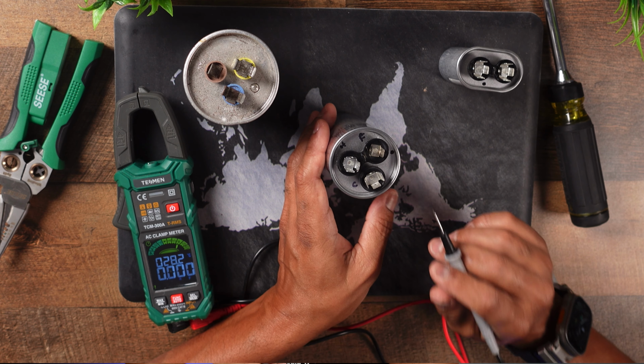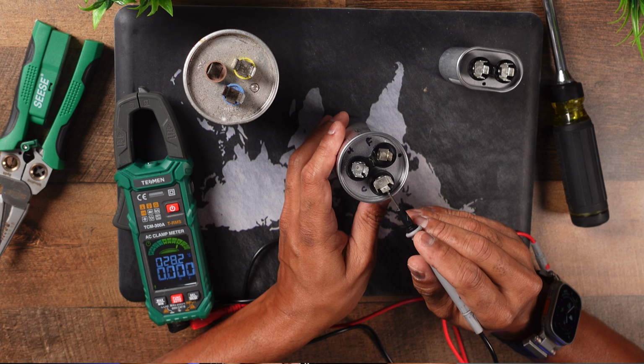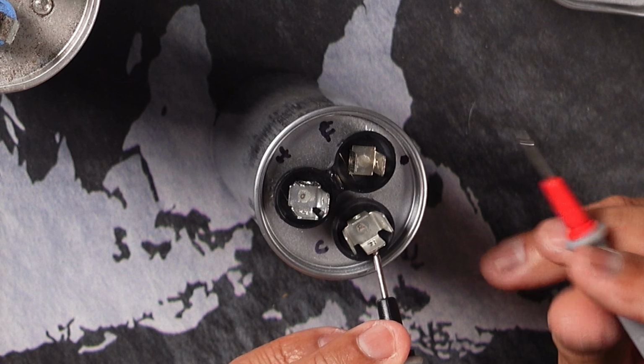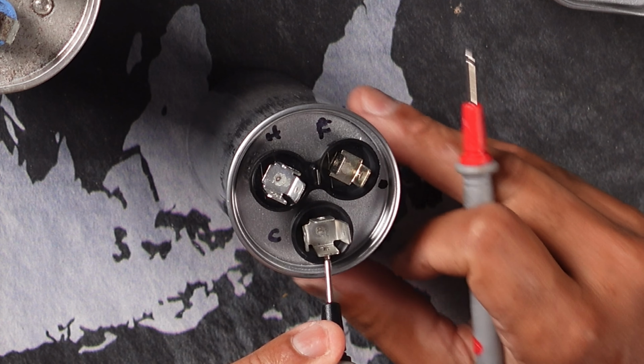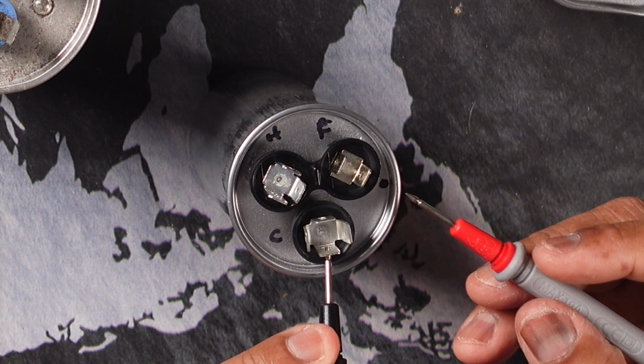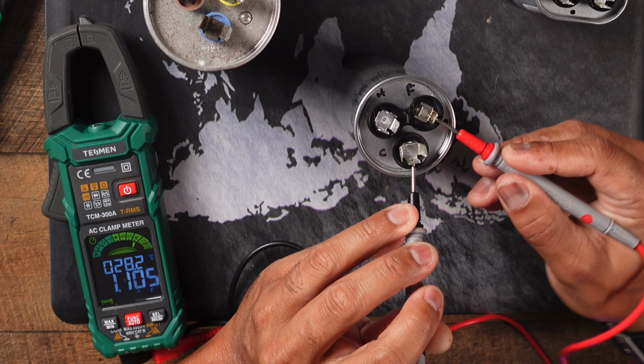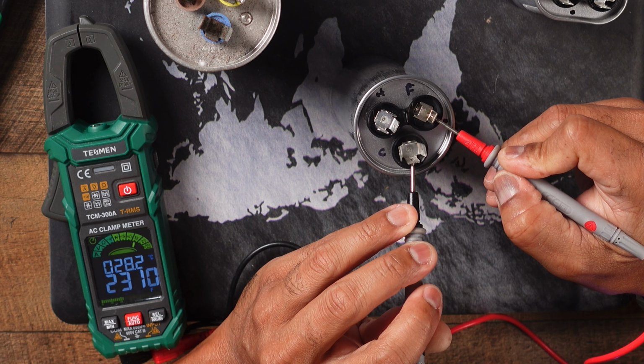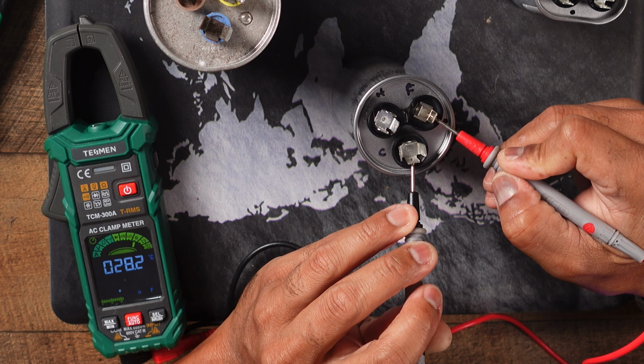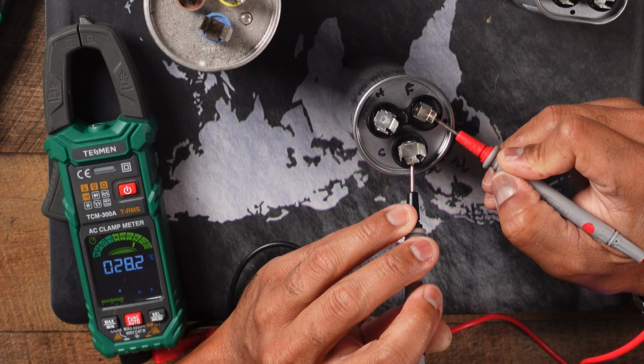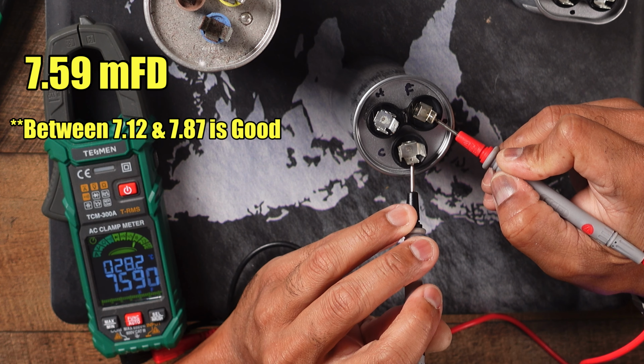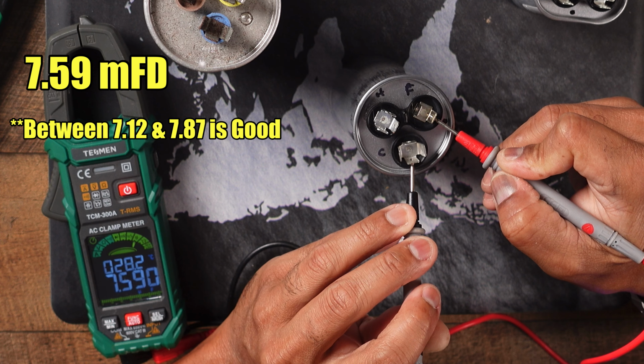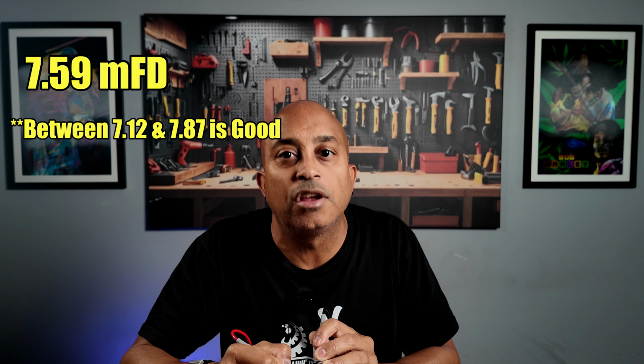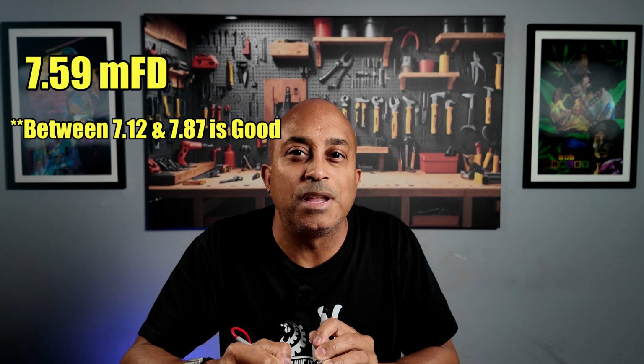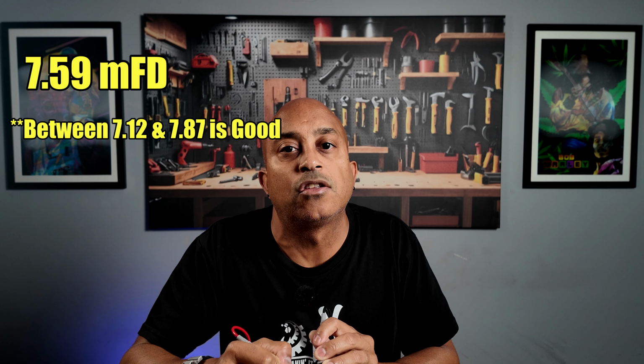Now that we have our meter set, place one probe on the C terminal and the other on the fan terminal, and hold it there for a second. Let it register and your meter should give you a reading. Mine says 7.59 microfarad, which is within the allowed tolerance, meaning the fan side of my capacitor is good.